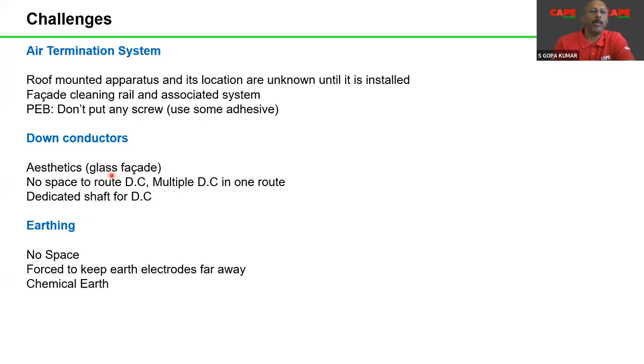You cannot do that. You route all the down conductors through one side of the building. So all the three sides are glass. You cannot touch that particular part. Your whole lightning protection down conductor has to be routed through one side. Practically, this is a violation of the standard. Your lightning protection system will not work. The second case, there is no space to route the down conductor. Third case, multiple down conductors in one route. All these are actually violations of the standard.